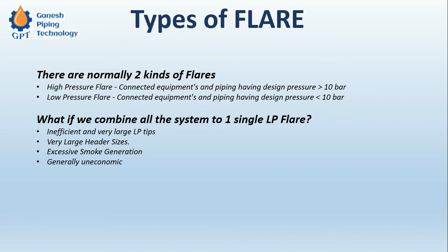If we combine all systems into one single LP flare, the consequences include inefficient and very large LP tips — the tip being the portion where the fire is visible — very large header sizes which are undesirable from an economy and operations standpoint, excessive smoke generation, and general uneconomy. To avoid all these issues, we use two flares: a high pressure flare and a low pressure flare.